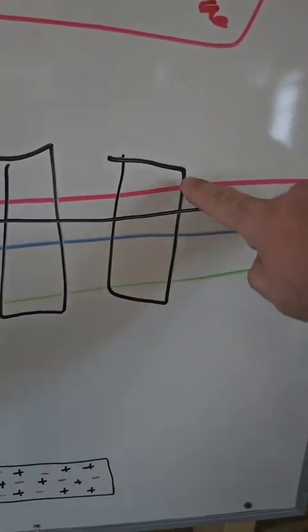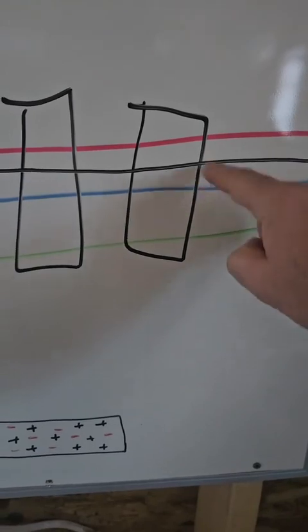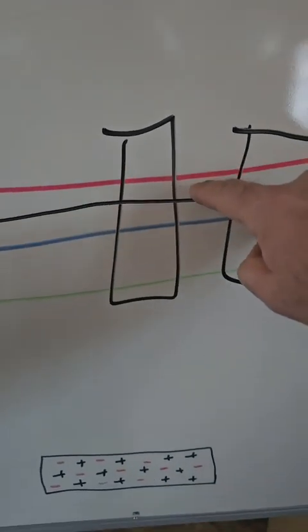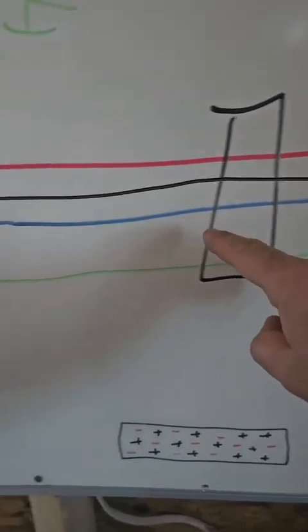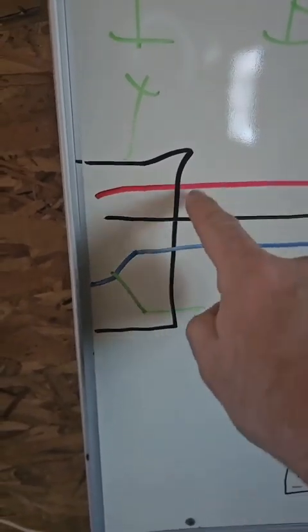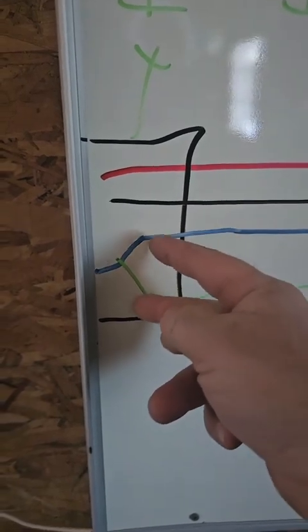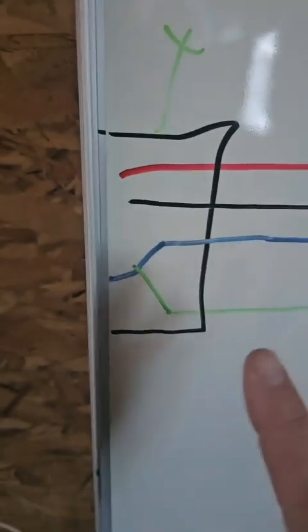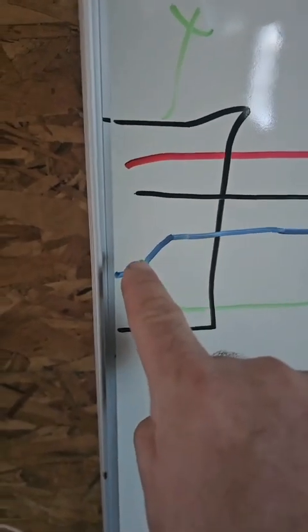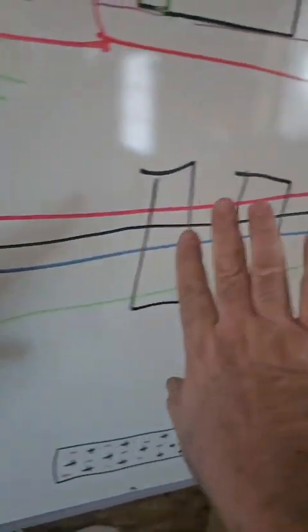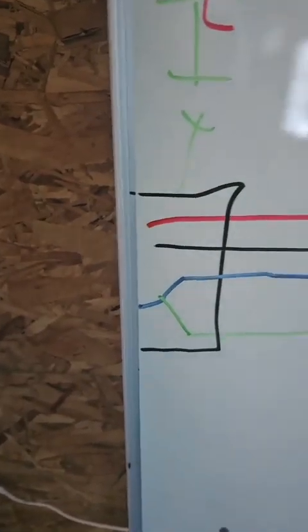This is a subpanel. Hot, hot, neutral, ground, not together. Subpanel, hot, hot, neutral, ground, not together. But in the main panel, you've got the hot, hot, the neutral, and the ground. When the neutral and ground enter the main panel, where the first point of disconnect is, it's going to be a main panel, maybe a meter socket, but one time they connect in order to create this connection. This happens one time. Throughout the house, they stay separate, but that one time here, they connect.